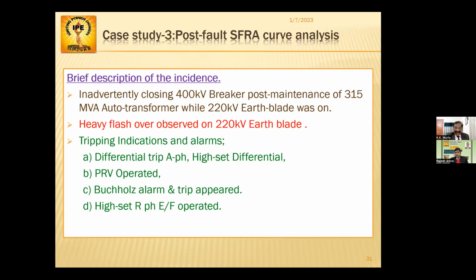And number 3 case study is a post-fault SFRA analysis. Brief description of the incident: inadvertently closing the 400 kV breaker post maintenance of a 315 MVA auto transformer. This is a 400 by 220 kV, 315 MVA transformer, while the 220 kV earth blade was on. So what was the observation? Heavy flashover observed on the 220 kV earth blade. Tripping indications and alarms appeared: differential trip A phase, high set differential, PRV operated, Buchholz alarm and trip appeared, high set R phase earth fault operated.